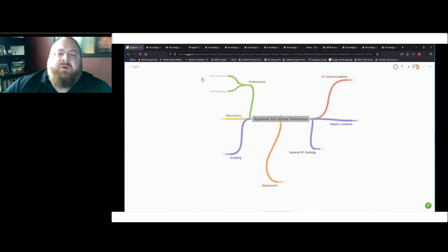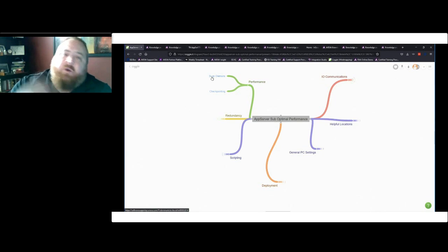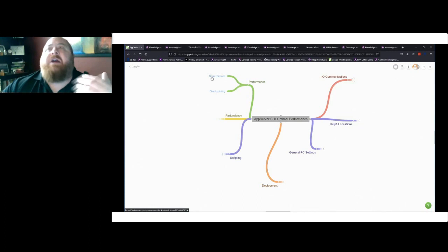Okay, so let's talk about app engine health quickly from a performance perspective. Back to my example earlier where I talked about the clock hanging on the wall. That's your engine scan, right? That's a deterministic process, and it runs as a Windows process. You're guaranteed that if it's 2017 or older, it's 1,000 milliseconds. If it's newer, it's 100 milliseconds. You're guaranteed it's going to execute consistently every time in that time. If it's not, that could be an indication there's something going on.